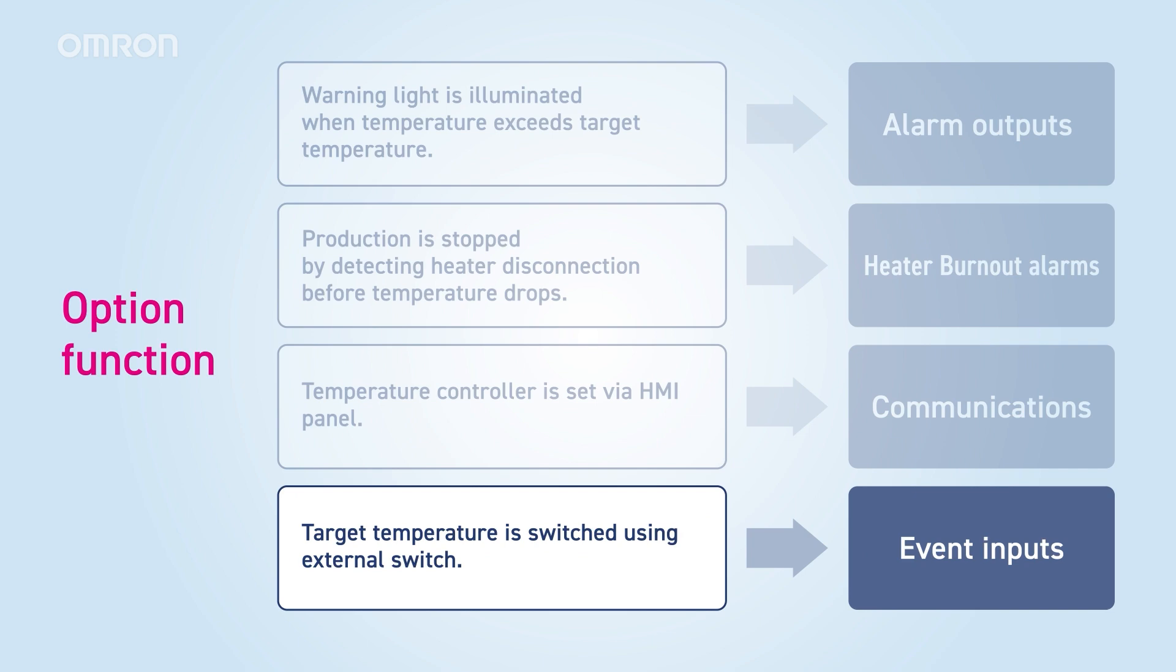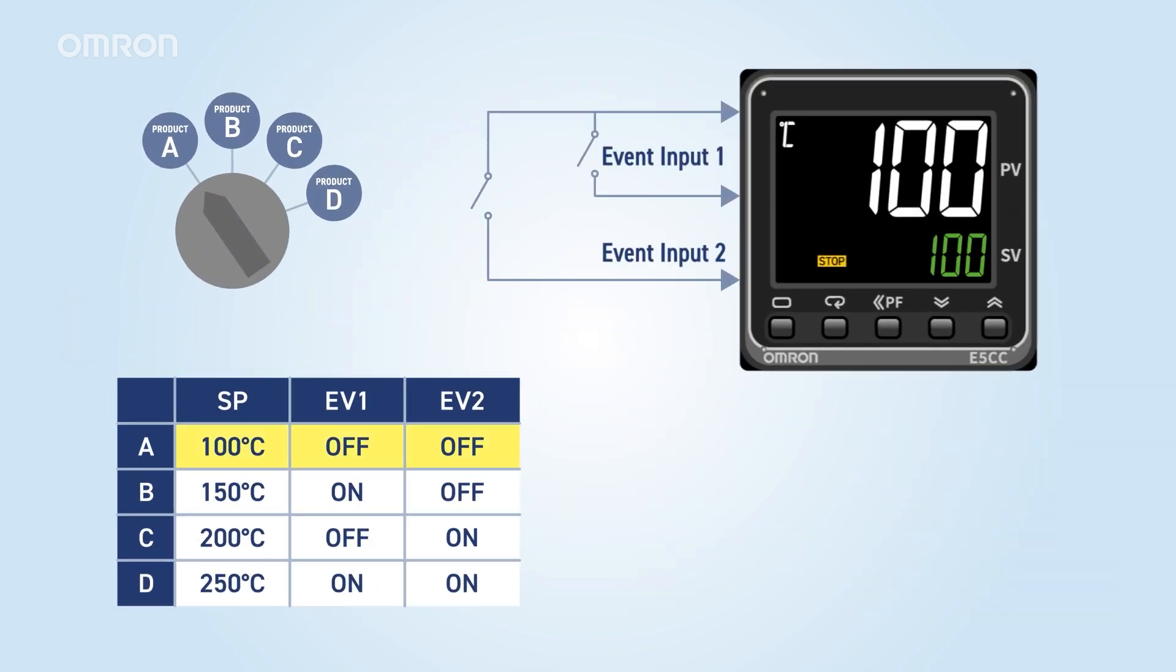Finally, let's explain event inputs. Event input allows you to change the settings of the temperature controller or issue operation commands like run-stop using external signals. For example, you can use an external switch to change the set temperature for each product, helping to prevent setting errors.